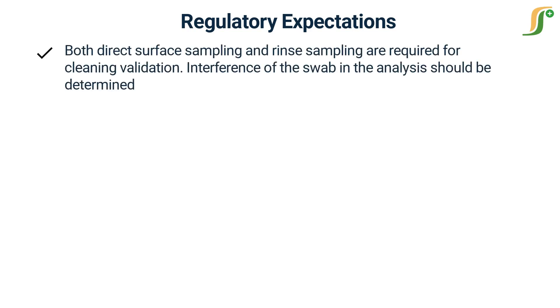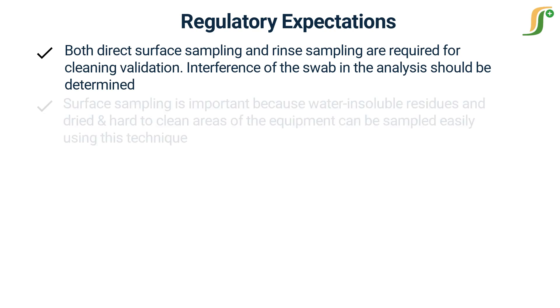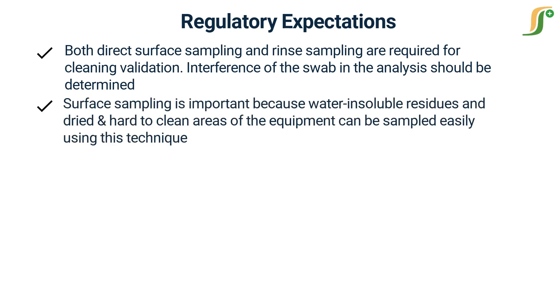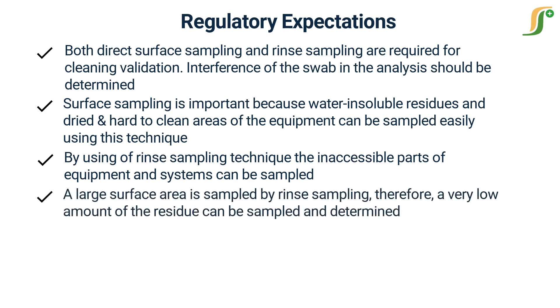Both direct surface sampling and rinse sampling are required for cleaning validation. Interference of the swab in the analysis should be determined. Surface sampling is important because water-insoluble residues and dried, hard-to-clean areas of the equipment can be sampled easily using this technique. Using rinse sampling, the inaccessible parts of equipment and systems can be sampled. A large surface area is covered by rinse sampling, so a very low amount of residue can be sampled and determined.